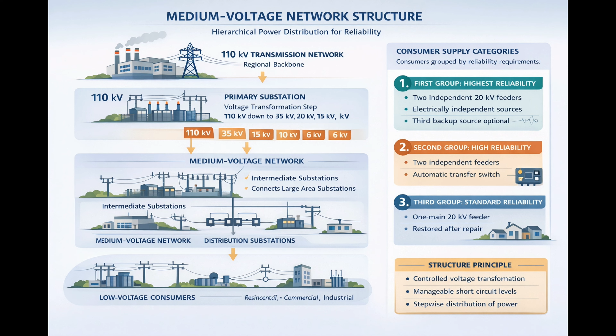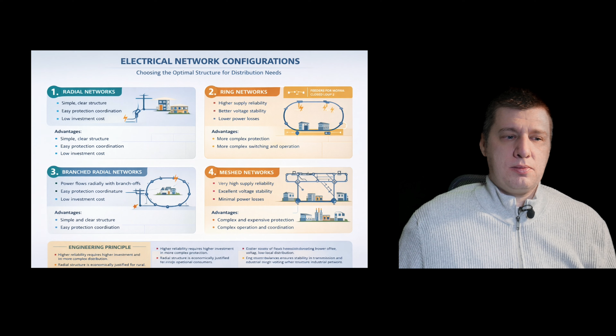As an engineer, you must understand voltage level hierarchy, the substation's role in the transformation, feeder structure, and consumer reliability categories. All those elements form one coordinated system. Medium voltage network structure is not random. It reflects technical constraints, economic limits, and reliability requirements. Electrical network configuration describes how branches and nodes are interconnected. Based on the structure, distribution networks are divided into four main types: radial networks, branch radial networks, ring networks, and mesh networks. Each configuration has clear advantages and disadvantages. Your task as an engineer is to select a structure that matches reliability, cost, and protection requirements.